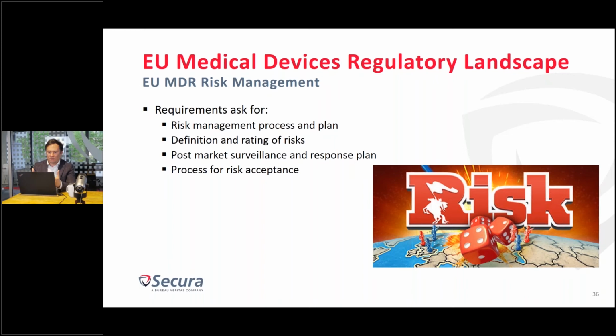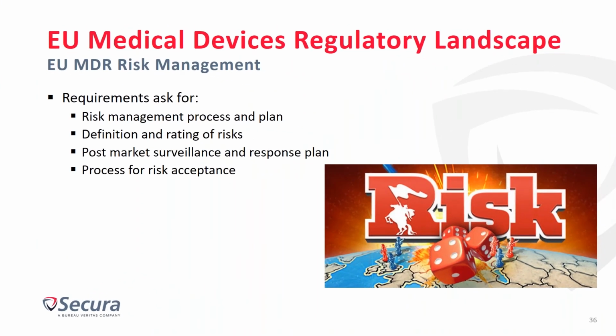The EU MDR is also asking for the process itself that was followed by the developer, also for the plan for risk management — the scope for performing the risk management on the product, the definition and final rating of the risks, and also very important, a plan for how the medical device manufacturer will perform this kind of risk management after the product gets on the market, so post-market surveillance and response plan.